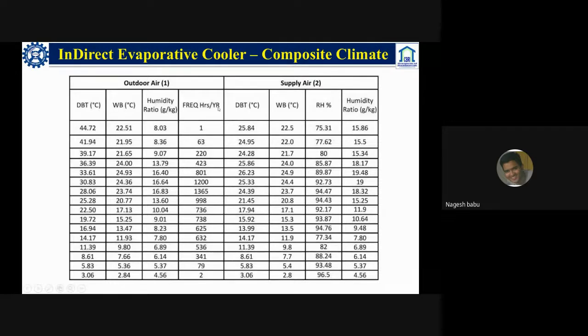If we look at typical temperature conditions using an indirect evaporative cooler, a composite climate has all types of conditions. So we have taken a composite climate and simulated the indirect evaporative cooler. On a typical day with an outside temperature around 45 degrees centigrade, it can reduce the temperature to 25 degrees centigrade. We achieve this cooling without a compressor and without refrigerant. As I have told you, the comfort condition is around 27.5 degrees centigrade, so achieving 25 degrees centigrade is well within the comfort zone. That is the advantage of using an indirect evaporative cooler: without a compressor and without a refrigerant, we can meet this temperature.